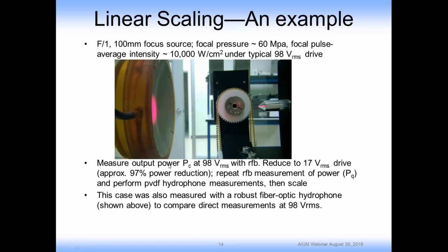This was measured, as I said, for total output power at around 100 volts RMS with a radiation force balance, so we could get the total output power of around 100 watts in this case. Then the driving voltage was reduced to 17 volts RMS. That's basically around a 97% power reduction. Power measurements were repeated in order to help with the scaling, as we'll discuss later on. And PVDF hydrophone measurements were made with this and then scaled, as we'll discuss. This picture also shows the use of one of these robust hydrophones, in this case a fiber optic hydrophone, so that we could actually compare the scaled measurements to some direct measurements that were performed at 98 volts RMS.